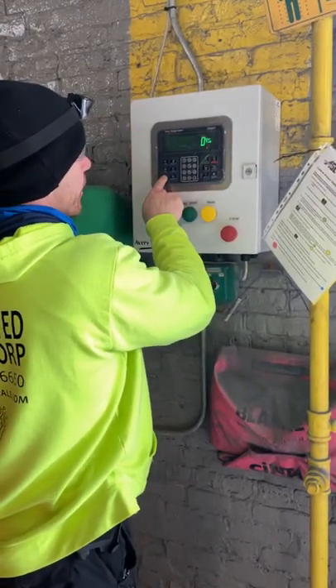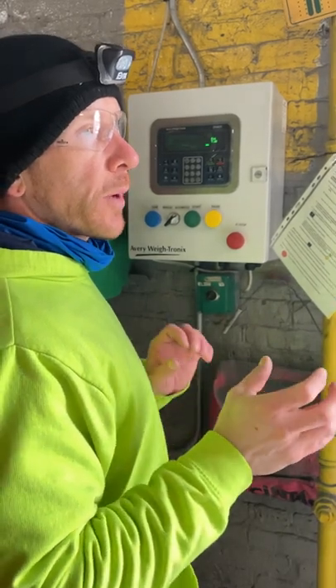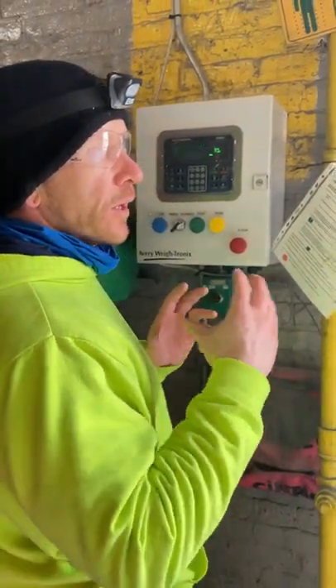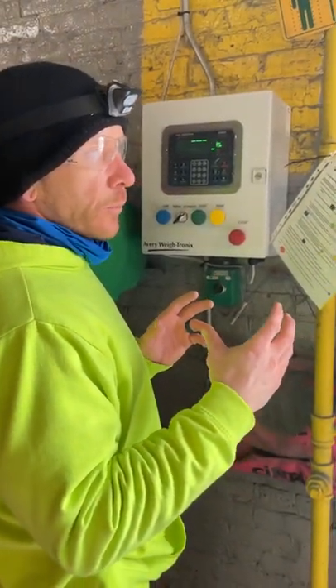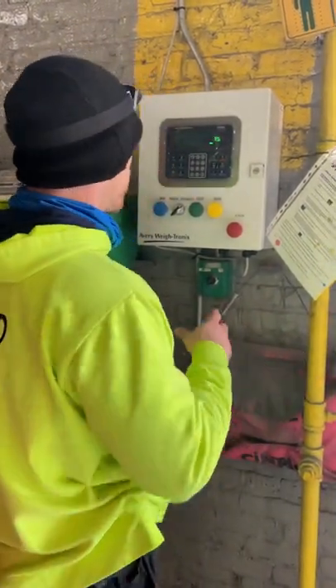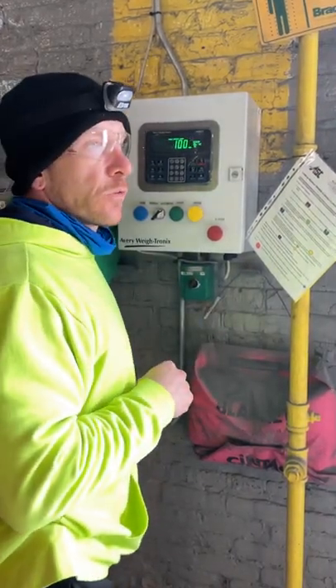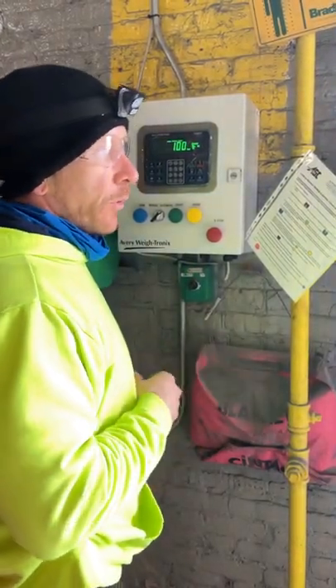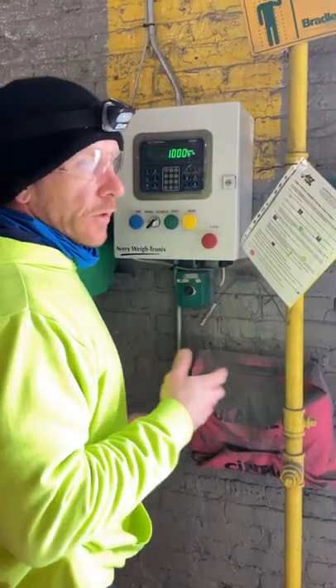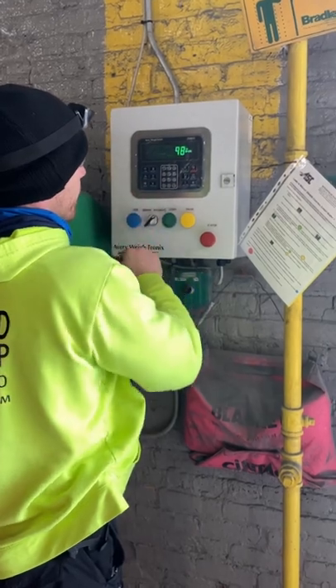The end time: this is if you want to switch back to the gross mode view off the inverted view when you're filling. If you set it to zero, it'll just always show the inverted view — I'm going to keep it at zero. Enter. And this is max weight to withdraw out of a pull. We set it to a thousand just so they don't accidentally set the target weight higher than that.